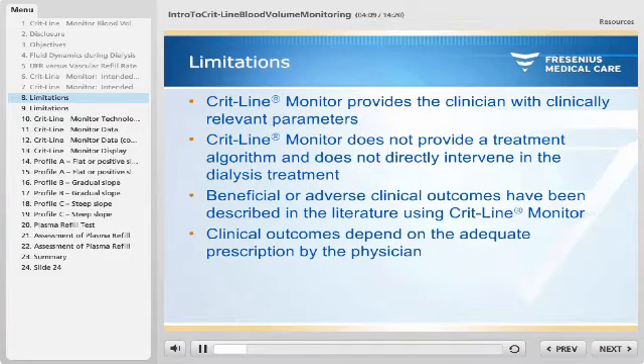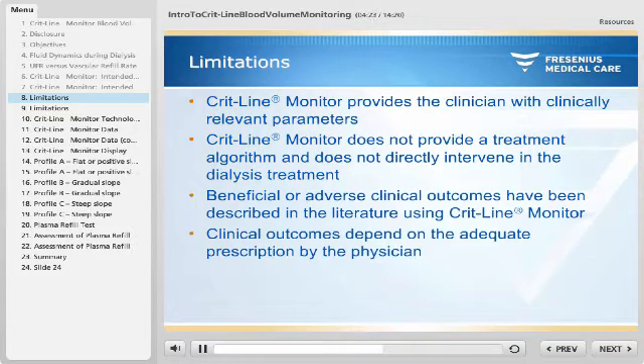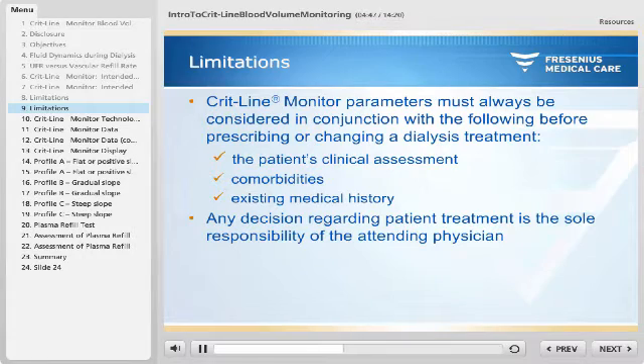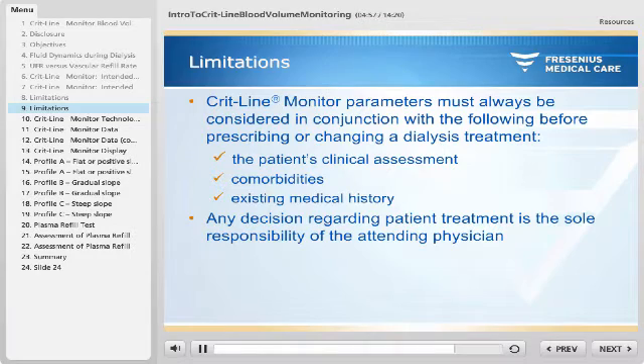When using the CRITLINE monitor, it is important to recognize its limitations. While it provides the clinician with clinically relevant parameters, the CRITLINE monitor does not provide a treatment algorithm and does not directly intervene in the dialysis treatment. Clinical outcomes depend on the adequate prescription by the physician. The CRITLINE monitor parameters must always be considered in conjunction with the patient's clinical assessment, comorbidities, and existing medical history. Any decision regarding patient treatment is the sole responsibility of the attending physician.